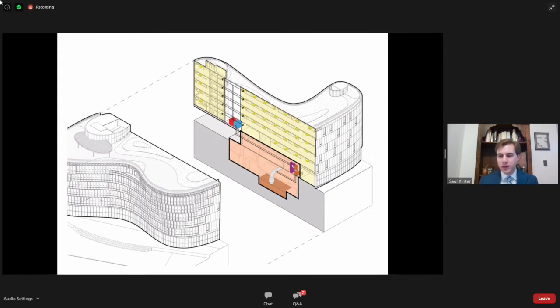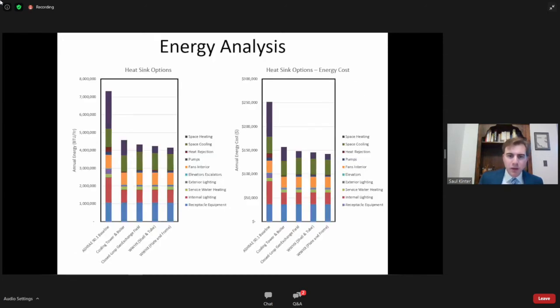The advantage is that in the winter, the sewage is at about 58 degrees Fahrenheit. So we can extract heat very efficiently. The delta T between 58 and the building's temperature at maybe 72 or 75 is quite small. And the heat pump doesn't have to work very hard. It doesn't have to use a lot of energy to warm the building up. Likewise, in the summer, the sewage is at about 78 Fahrenheit. So the net result is that we're able to reduce energy, if we can go to the next slide, by something like 40 to 45% beyond the ASHRAE baseline. And even versus a cooling tower application, we're able to get several percentage points of improvement in terms of both the energy consumed and the cost of operation.